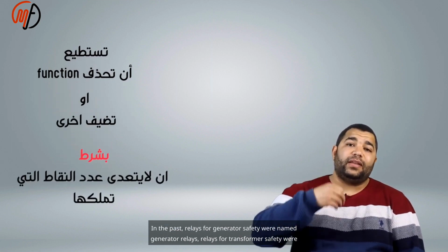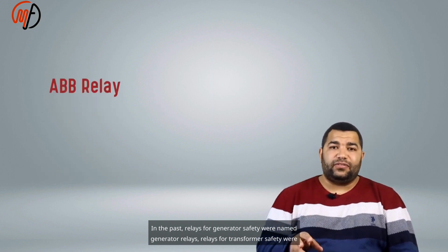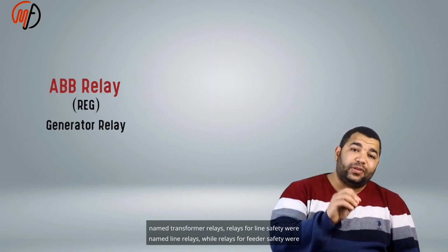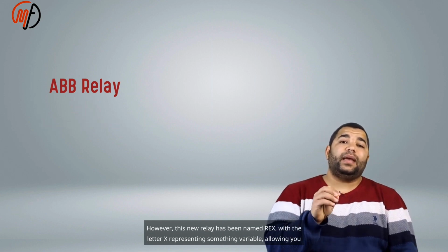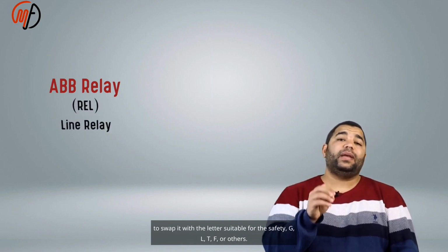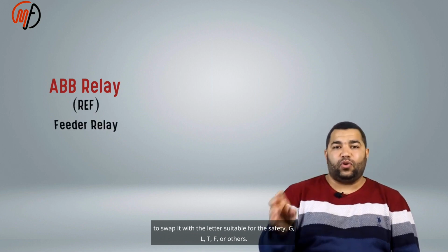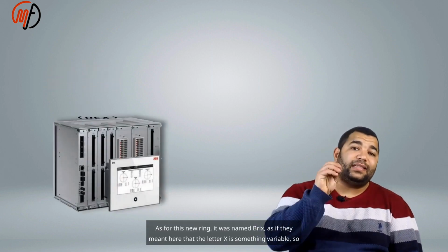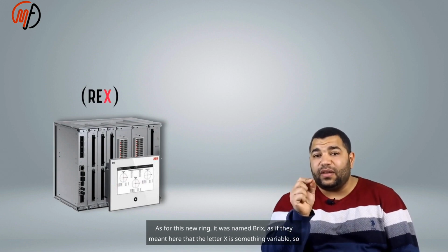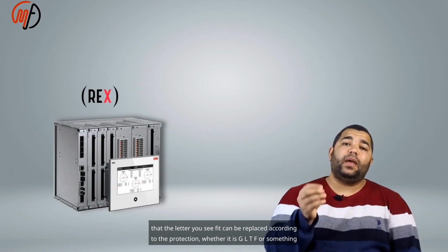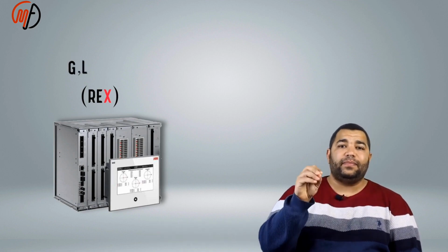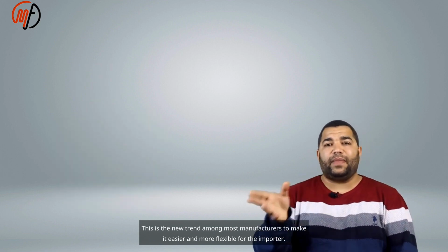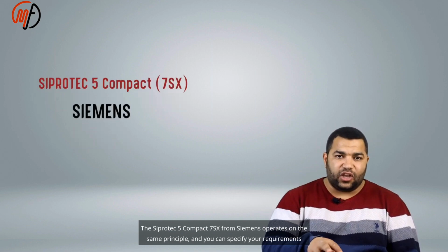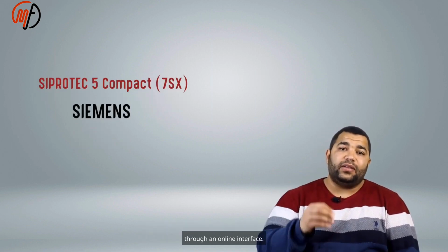In the past, relays for generator safety were named generator relays. Relays for transformer safety were named transformer relays. Relays for line safety were named line relays, while relays for feeder safety were named feeder relays. However, this new relay has been named REX, with the letter X representing something variable, allowing you to swap it with the letter suitable for the safety, G, L, T, F, or others. As for this new relay, it was named REX, as if they meant here that the letter X is something variable, so that the letter you see fit can be replaced according to the protection, whether it is G, L, T, F, or something else. This is the new trend among most manufacturers to make it easier and more flexible for the importer. The Siprotec 5 Compact 7SX from Siemens operates on the same principle, and you can specify your requirements through an online interface.